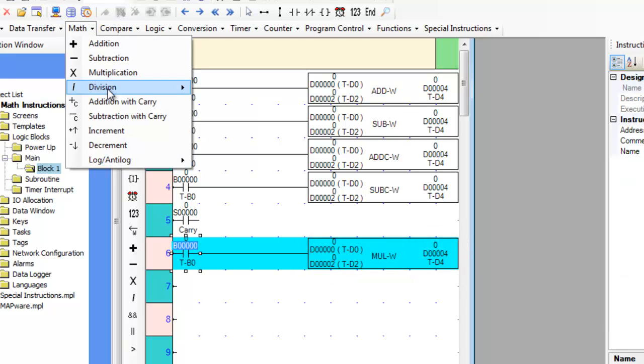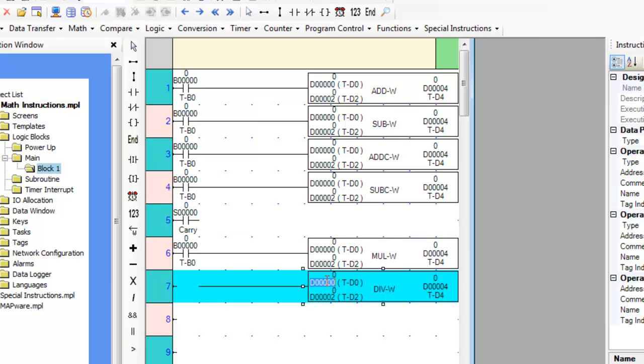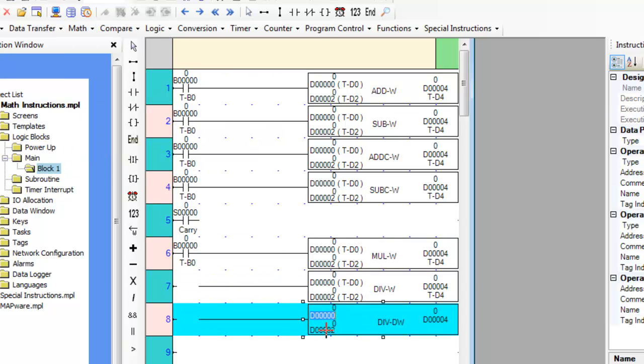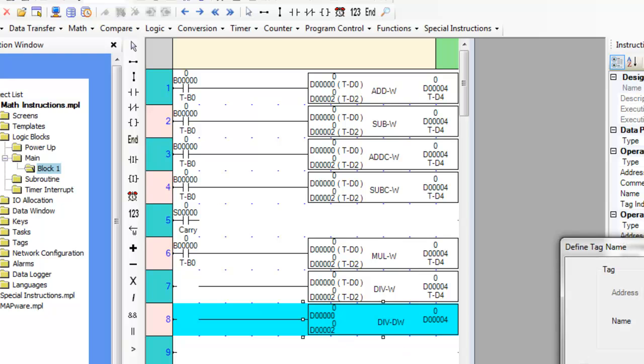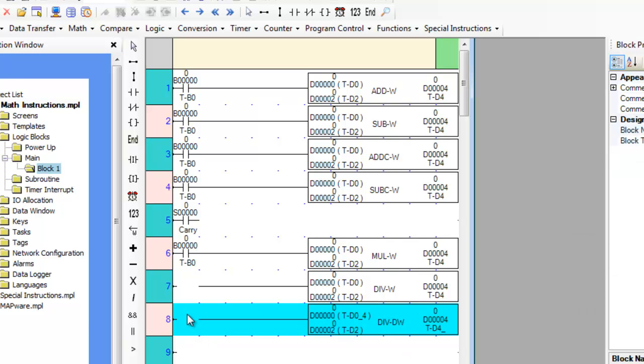The division instructions will divide the value in register A by the value in register B when the rung is true. The result is placed in register C and the remainder of the division is placed in register C plus 1. For example, if register C is D10, the quotient is placed in D10 and the remainder is placed in D11.